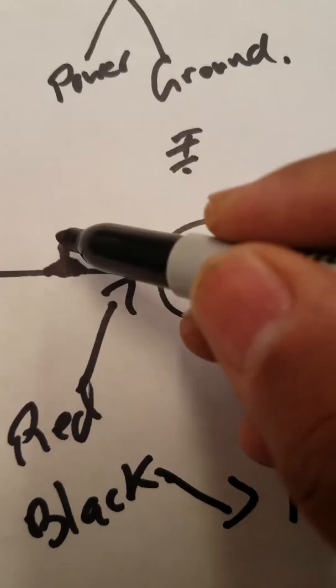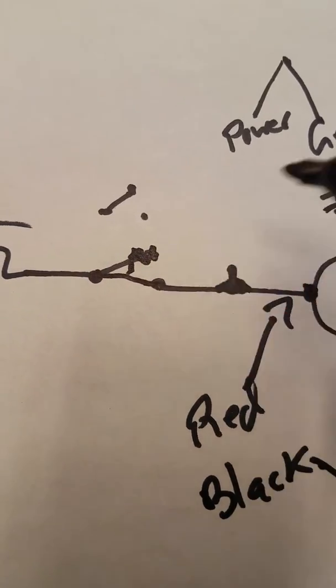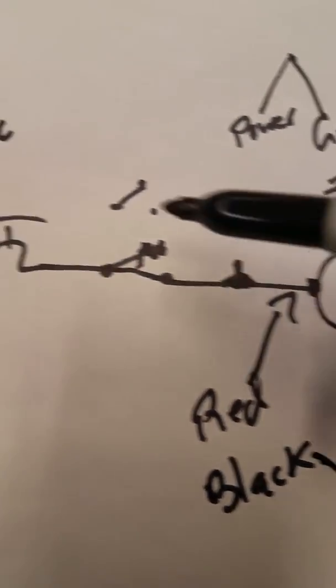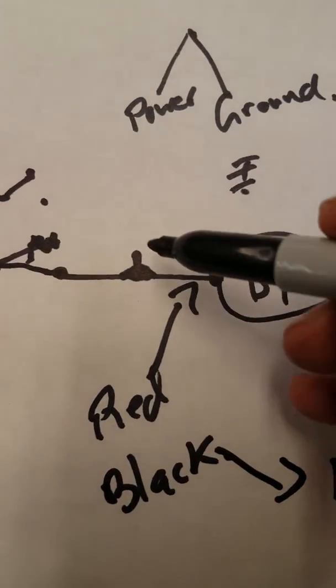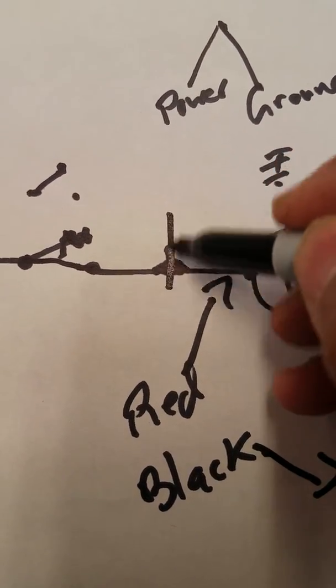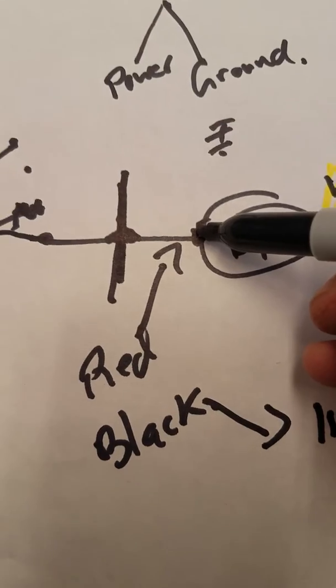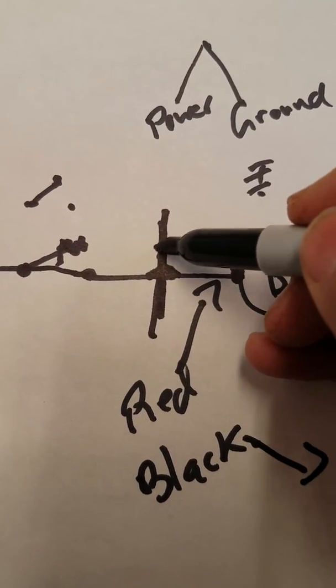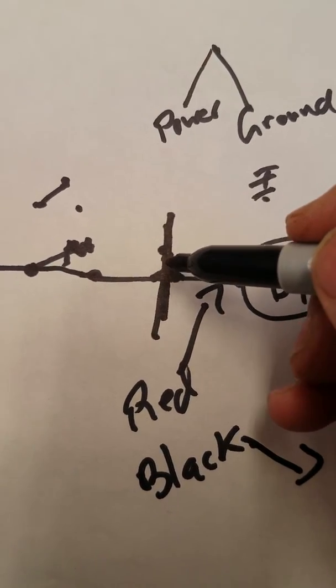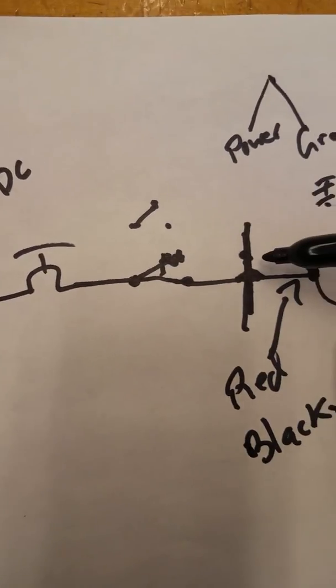But let's say there is no power at the boost pump. The switch is closed, the current came through the terminal strip, but it didn't make it to the pump. What do you do — go all the way back to the bus? No. You go somewhere in the middle. In a long circuit, find the midpoint — in this case, the terminal post — and check for power there. Red lead on power, black lead on ground, meter set to 28 volts DC or higher range.